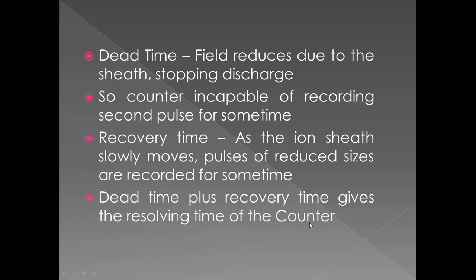Resolving time means the time in which, after recording an event, the GM counter is again ready to record the next event. So that is the resolving time. The dead time, recovery time and resolving time are some parameters associated with a GM counter which need to be understood.